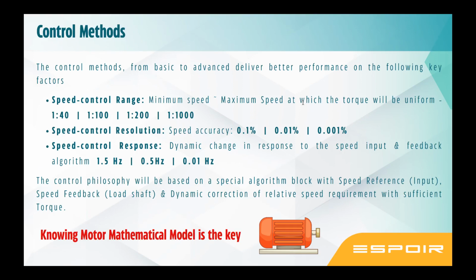When your application is demanding a low speed, high torque, continuous operation, you need to go for a closed loop method. You need to buy an encoder. You need to tune it. You need to adjust certain parameters to achieve that range.